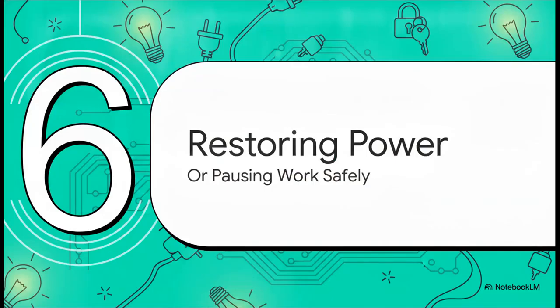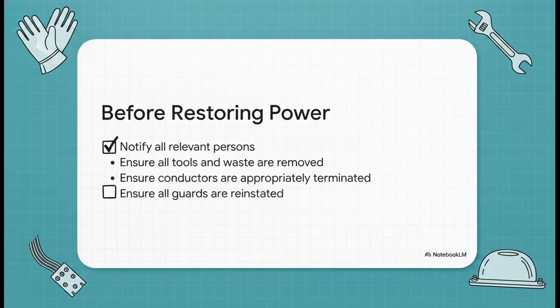And finally, Section 6, restoring power or pausing work. Restoring power is not just a matter of ripping off your lock and throwing the breaker. You need to treat this like a pilot's pre-flight checklist. These steps are completely non-negotiable. First, you must notify all affected personnel that the power is about to come back on. Then, you do a careful visual inspection. Are all your tools accounted for? Is all surplus material and garbage removed? Next, double-check that all conductors have been appropriately terminated and your mandatory testing is completely finished. Finally, make absolutely sure every single guard, cover, and barrier is fully reinstalled.